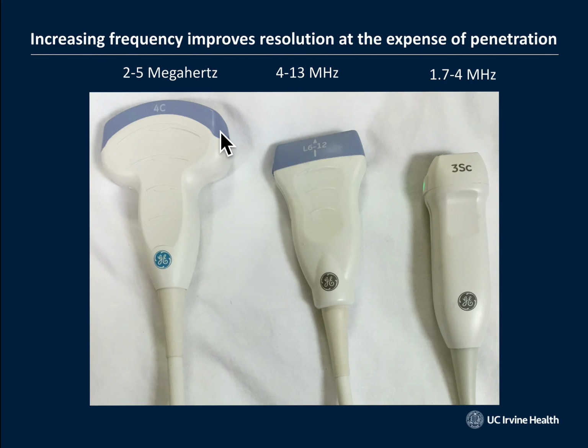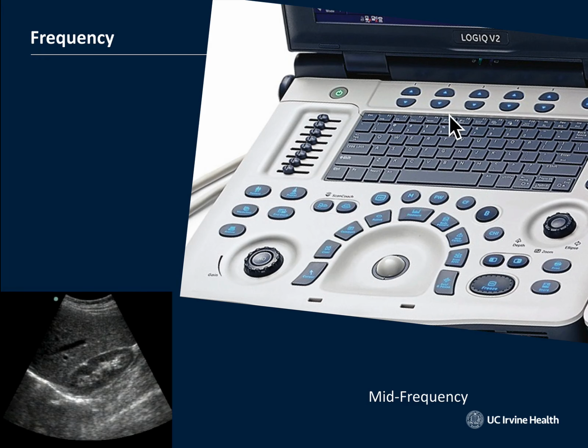And you can actually turn up and down the frequency within one transducer. Notice there's a range here, 2 to 5, 4 to 13, 1.7 to 4. So we can bump it up or bump it down using the controls here underneath the screen, this primary control panel. But so, you see this area here, this is like a mid-frequency, somewhere halfway between the two frequency bandwidths. Let's say if the probe goes from, like, I don't know, 1 to 5 megahertz, this would be the 3 megahertz setting here, and the dots are pretty close together, so a pretty resolute image.